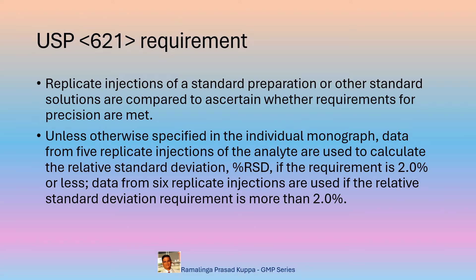data from 5 replicate injections of the analyte are used to calculate the relative standard deviation %RSD if the requirement is 2% or less, and data from 6 replicate injections are used if the relative standard deviation requirement is more than 2%. So, for %RSD less than 2%, data from 5 replicate injections is required.